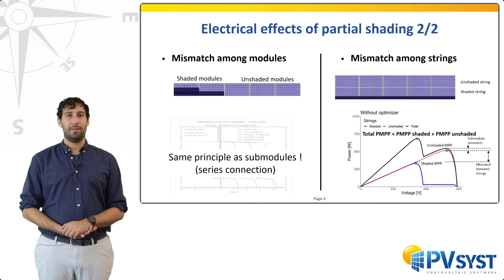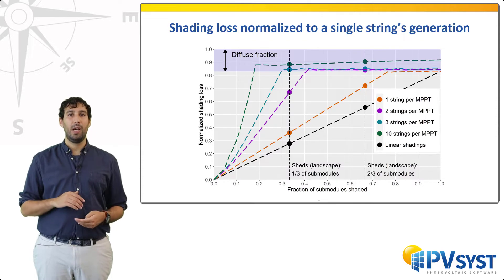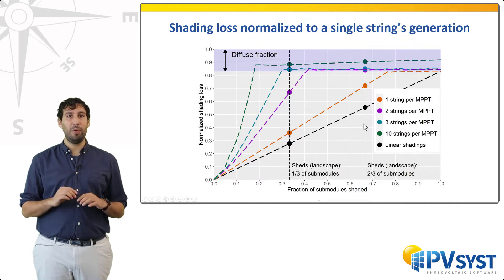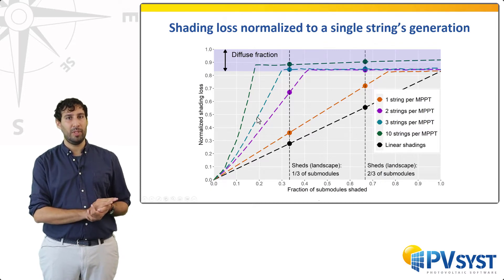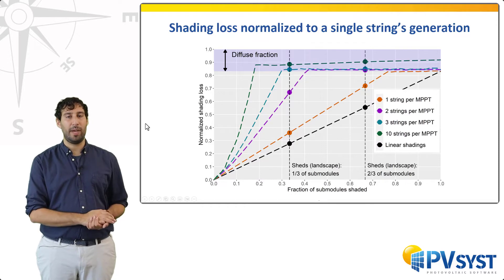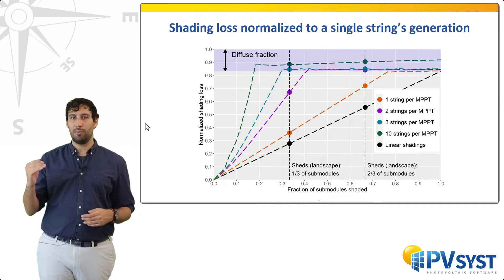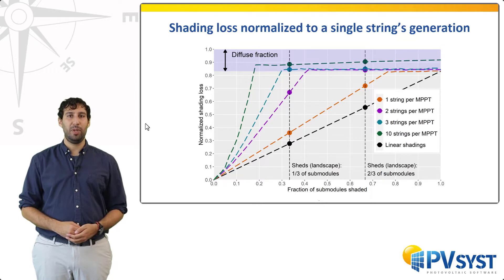This last situation can be generalized. In this plot, we study the shading losses normalized to the production of a single string as a function of the number of sub-modules being shaded. The inter-row shading situation corresponds to different points on the x-axis. In regular shadings on standard modules, one always shades one-third of all sub-modules at a time, hence the importance of the one-third line and the two-third line. A situation without mismatch corresponds to the black line. The orange line, where only one row of modules is connected to an MPPT, shows a few extra losses due to sub-module mismatch. The mismatch between strings will increase with the number of strings in parallel, and from two strings onwards one quickly reaches a plateau in the losses.